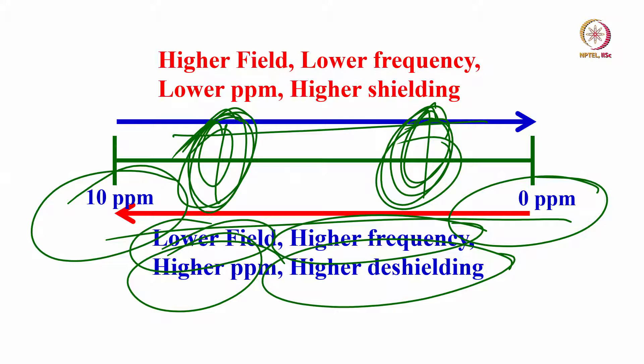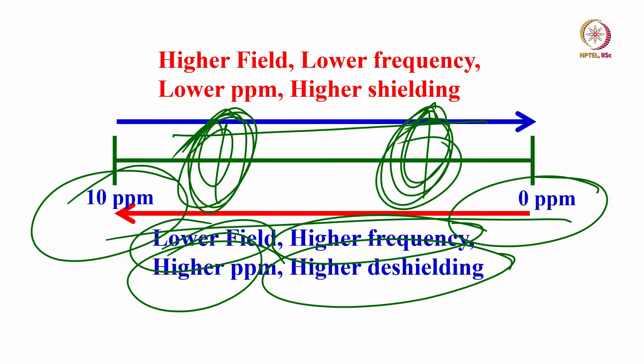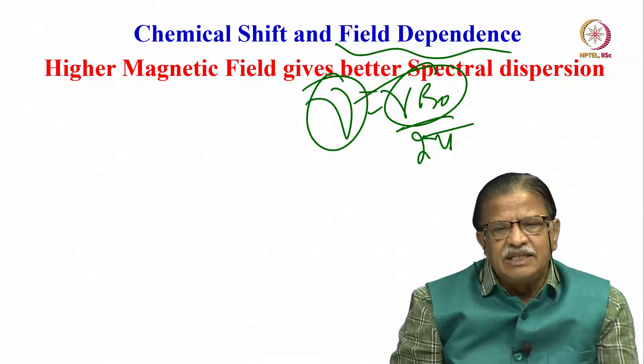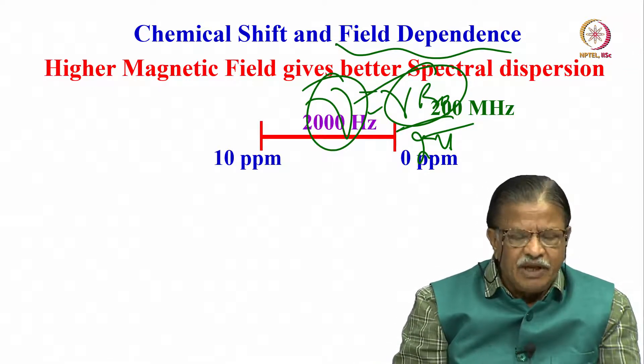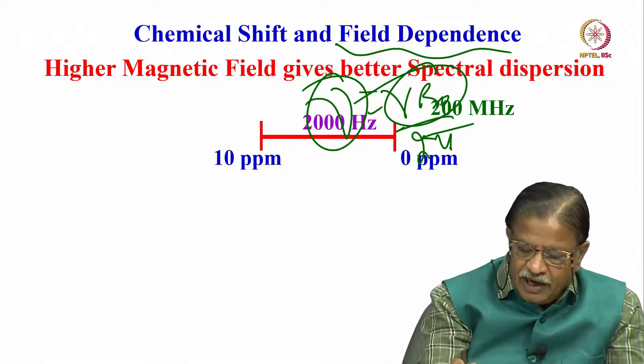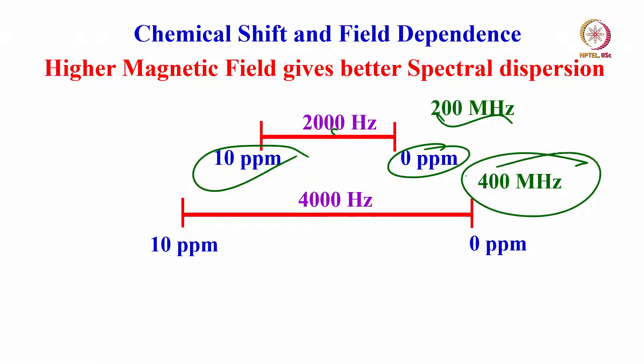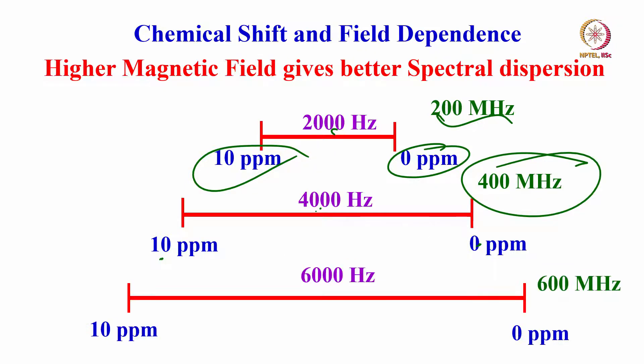Higher magnetic field gives better spectral dispersion — this is always true because ν = γB₀/2π. Resonant frequency varies linearly with magnetic field, so chemical shift also increases linearly. In a 200 MHz spectrometer, 0 to 10 ppm spans 2000 Hz for proton; in 400 MHz it spans 4000 Hz; in 600 MHz it spans 6000 Hz.